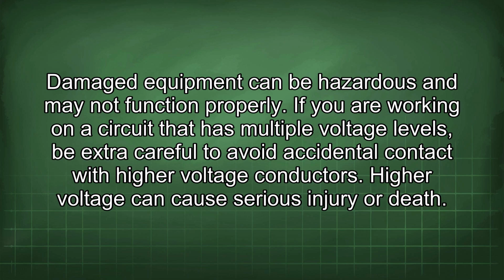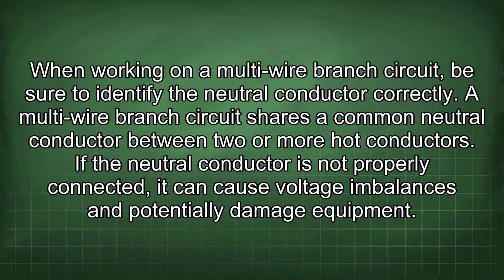If you are working on a circuit that has multiple voltage levels, be extra careful to avoid accidental contact with higher voltage conductors. Higher voltage can cause serious injury or death. When working on a multi-wire branch circuit, be sure to identify the neutral conductor correctly. A multi-wire branch circuit shares a common neutral conductor between two or more hot conductors. If the neutral conductor is not properly connected, it can cause voltage imbalances and potentially damage equipment.